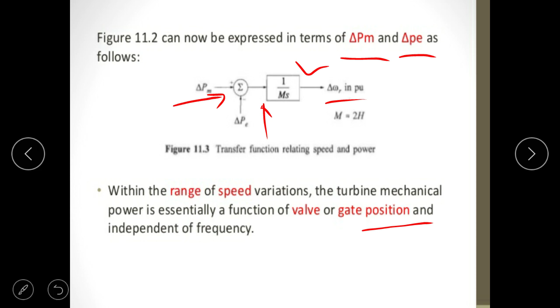Now it can be expressed in terms of delta Pm and delta Pe. Delta Pm is the change in mechanical power and delta Pe is the change in electrical power. So in this block diagram, delta Pm is the variation in input, delta Pe is the variation in output, 1 upon Ms is the gain function, and delta omega r is the variation in speed. Within the range of speed variation, the turbine mechanical power is essentially a function of valve or gate position, which is independent of frequency.